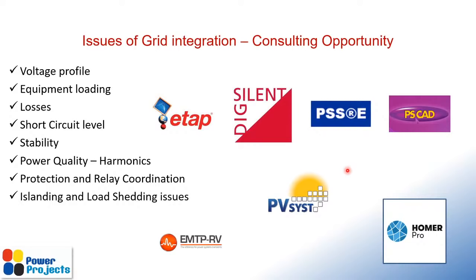The next important things I think I have already discussed. When you add wind or solar, it comes with an inverter or a converter that injects harmonics, and that also adds flicker issues. Protection and relay coordination is another big issue. Then islanding: if a part of the grid disconnects and operates along with the renewables, how do you manage the frequency, voltage and power quality issues? That's another concern. These are some of the problems which we are facing.